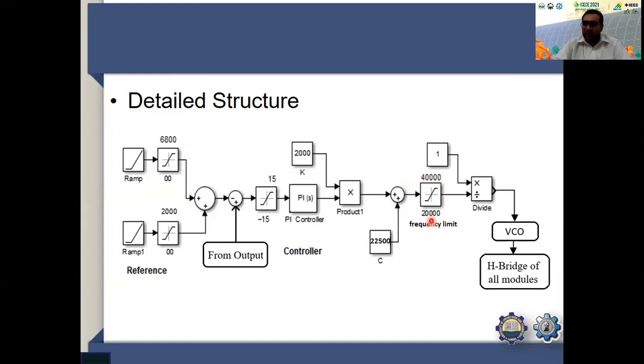We have put a minimum value of 20,000 and a maximum of 40,000 here. So it means that we are trying to control the output voltage by staying in the frequency greater than the resonance frequency, which was 20,000. Based on this frequency, it will generate a voltage level, and that voltage level will be fed to the VCO, and the VCO will be providing gating signals to the H-bridge modules, and based on the frequency of those gating signals, we will be controlling our output voltage.